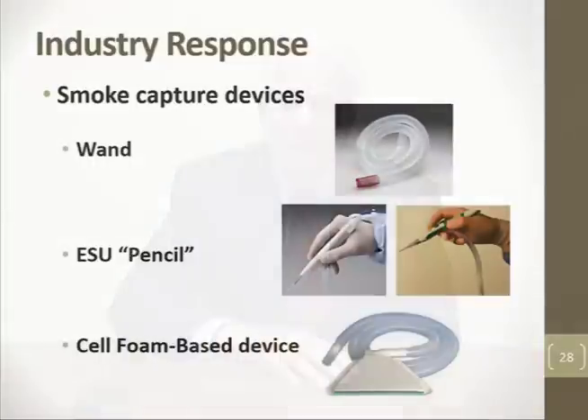The industry response we've really spoken about. The wand or the tube, and now the wand, as you can see in this photograph, really has evolved into a 7/8 inch corrugated hose called respiratory tubing with a sieve over it to prevent the possibility of a sponge being sucked into the tubing. Again, this was the original way in which smoke was captured. The problem with it is that it requires somebody to do it, and we don't have a free hand in the operating room anymore.